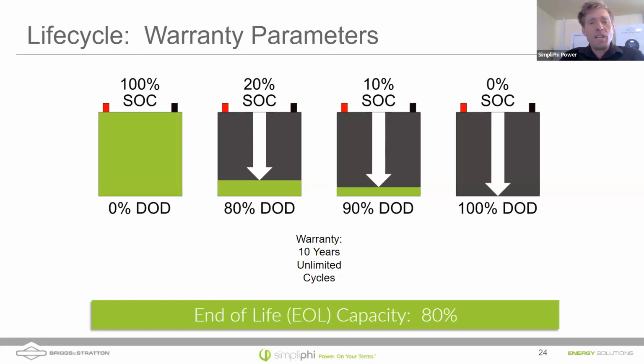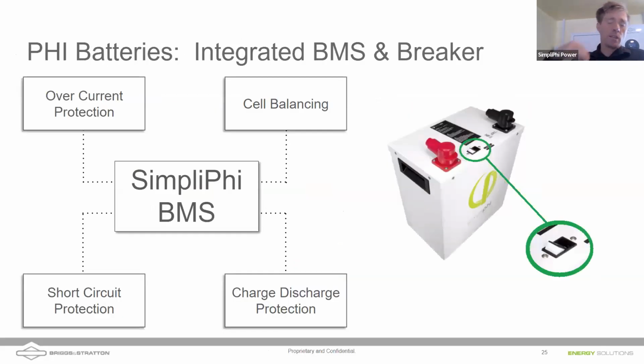Saving more than 20% of your battery, we get this question often, doesn't really seem to give a major increase in life expectancy. So we don't see an additional return of, if you only discharge to 30% compared to 20%. And so we don't really recommend any higher of a battery reserve. So keep these in mind as you're installing, depending on the customer's use. If they're intending to just do backup, maybe want to do 100% depth of discharge. And if they're doing daily cycling, we recommend that 20% left in the battery. And so I wanted to give you that background on life expectancy.